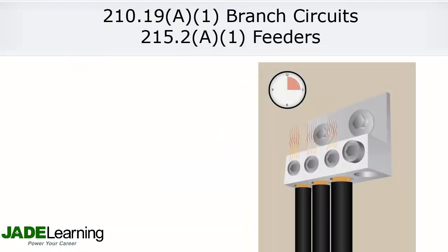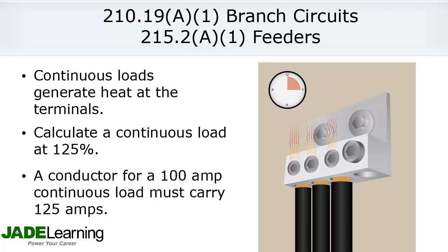Because of the extra heat that can be generated at the terminals where a conductor is terminated, all loads which will be on for more than three hours must be calculated at 125% of the continuous load. For example, a 100 amp continuous load requires a wire that will carry 125 amps.